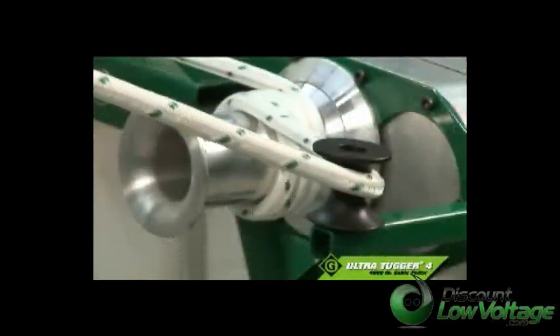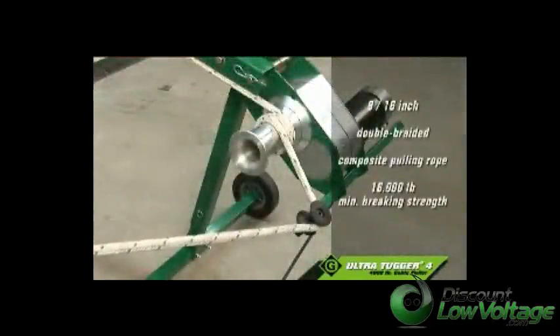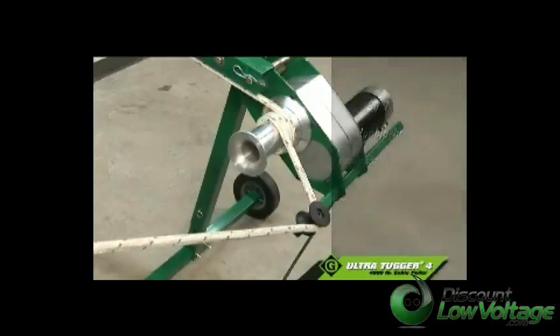As always, Greenlee recommends the right rope for the job. For pulling with the UT-4, we recommend 9-sixteenths inch double-braided composite pulling rope with a 16,000-pound minimum breaking strength.